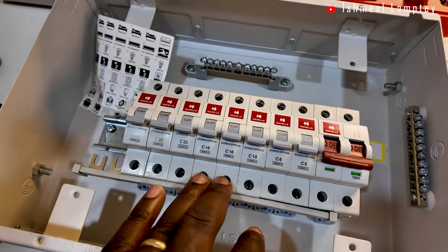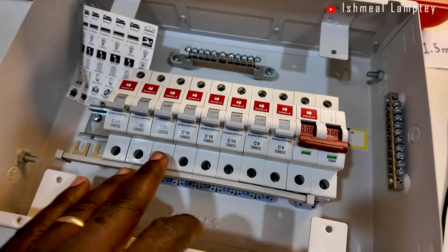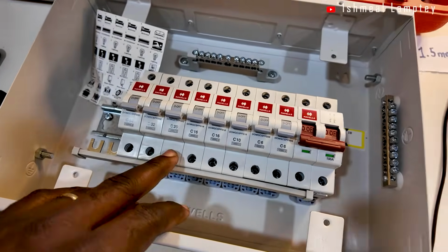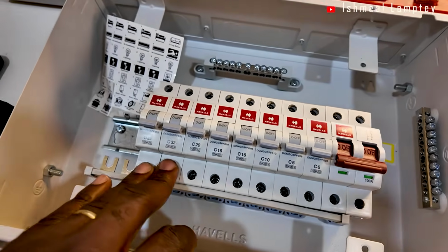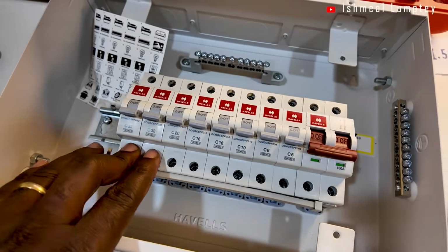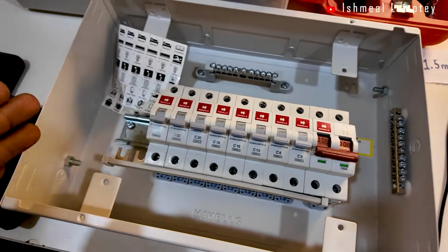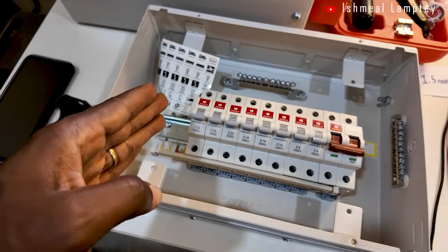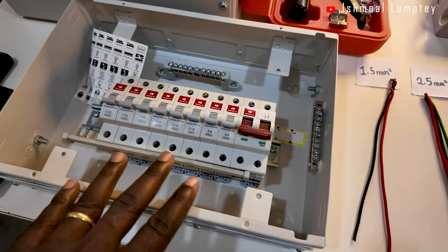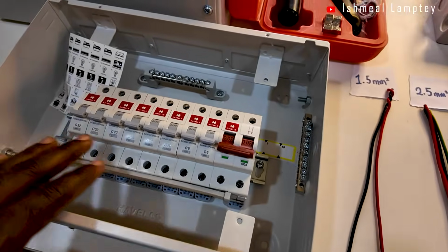Then you have 16 amps typically for sockets. You can also have 20 amps for sockets, especially when the circuits are more. Then you have 32 amps maybe for your cooker units, for air conditioners, among others. There are other sizes of breakers, bigger ones, for other purposes, but for this particular distribution, these are the breakers that fit here.